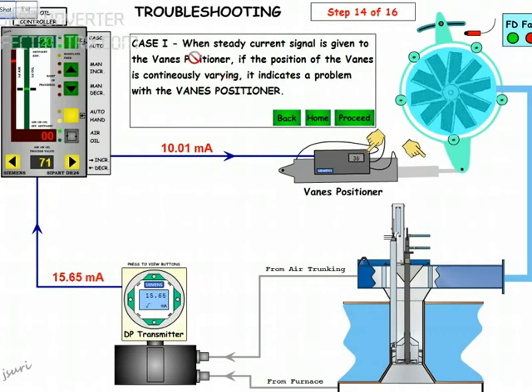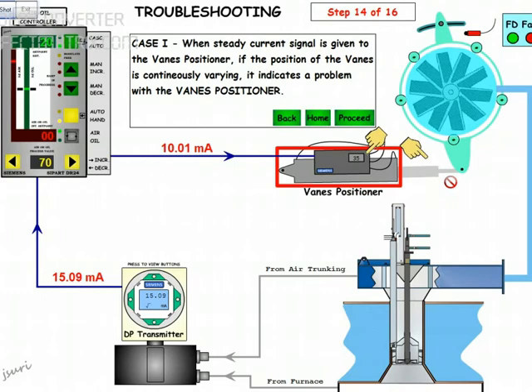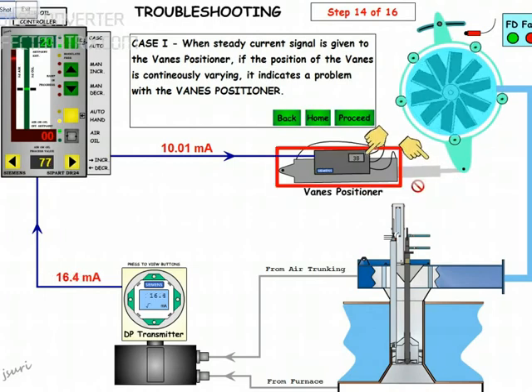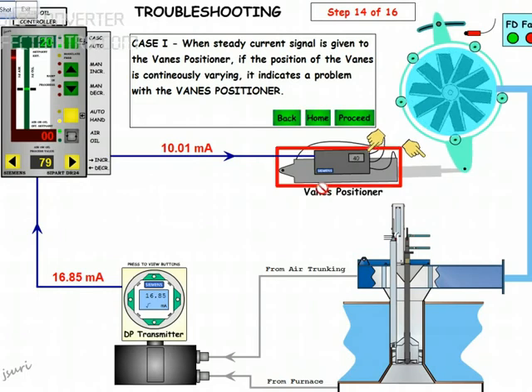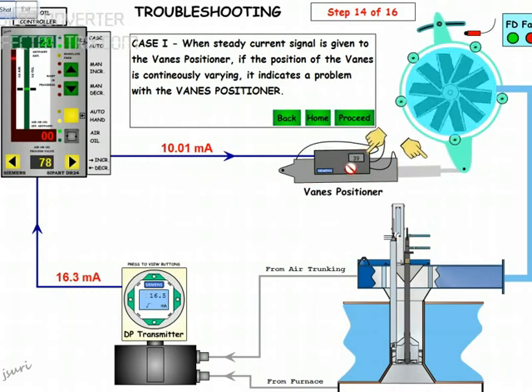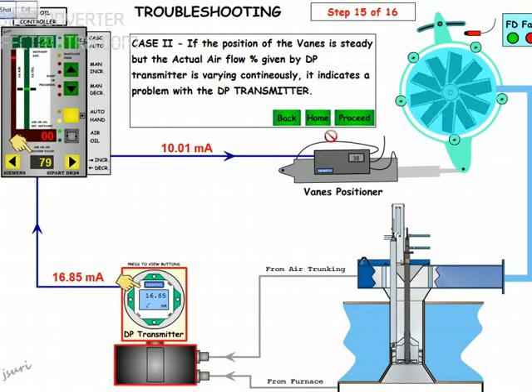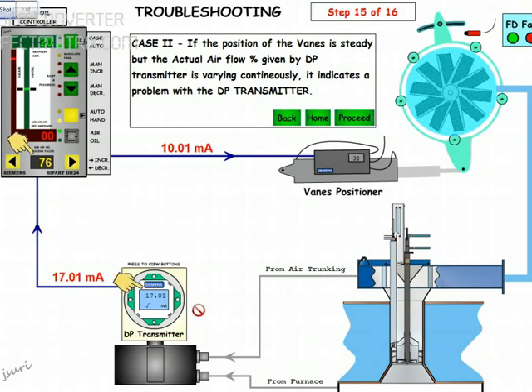Case 1: When a steady current is given to the vane positioner and you can see it is still fluctuating, that indicates the vane positioner is at fault — because with a steady current it should not be fluctuating like this. Case 2: When the current is steady and the vane position is also steady, there is no problem with the vane positioner; the problem is only with the DP transmitter. Change the DP transmitter and it will be okay.